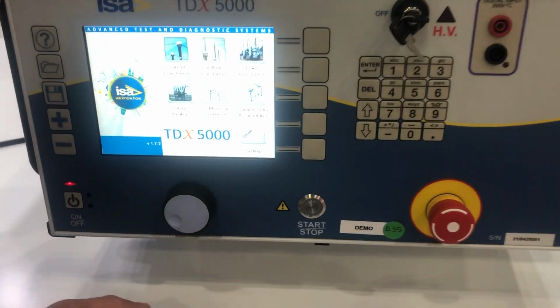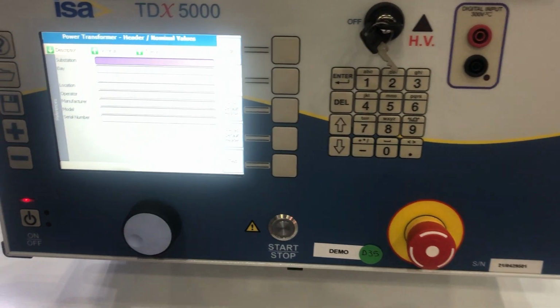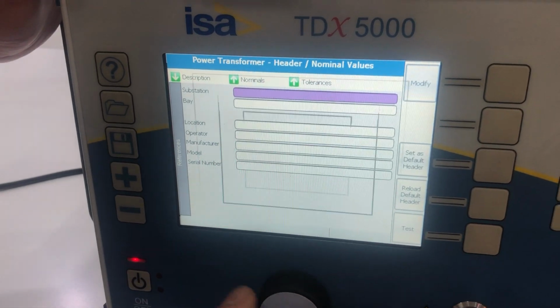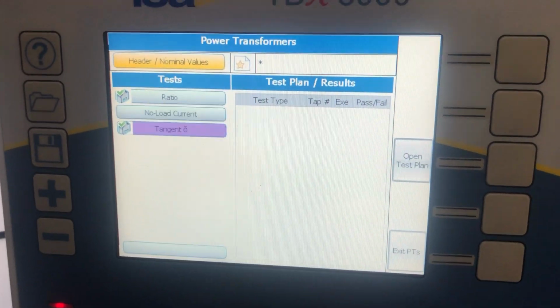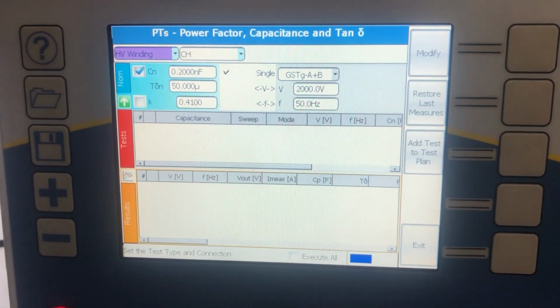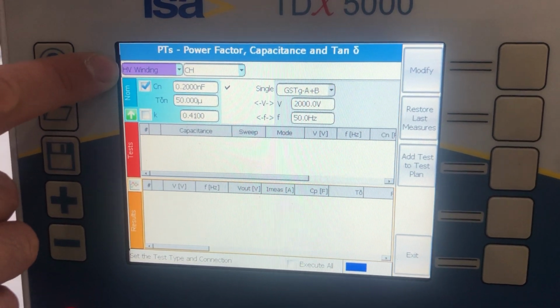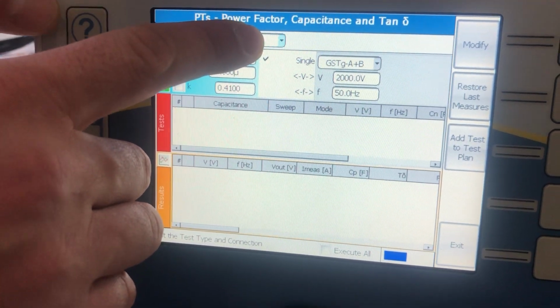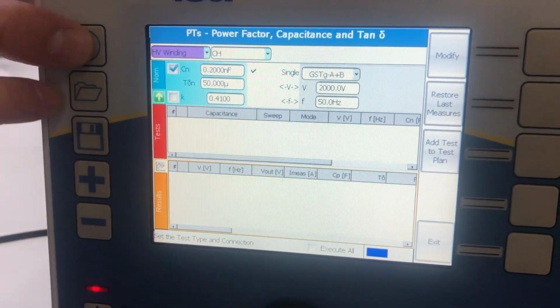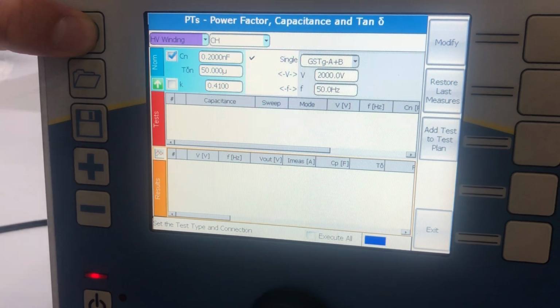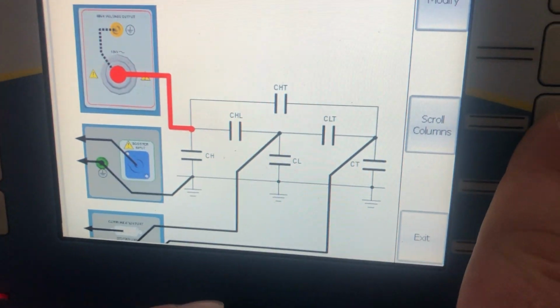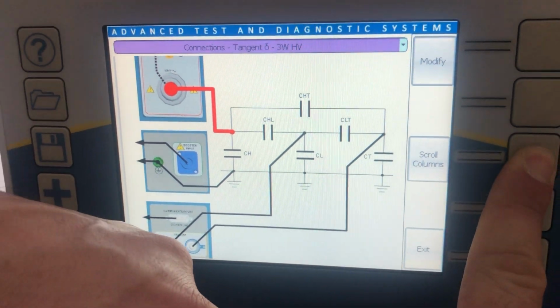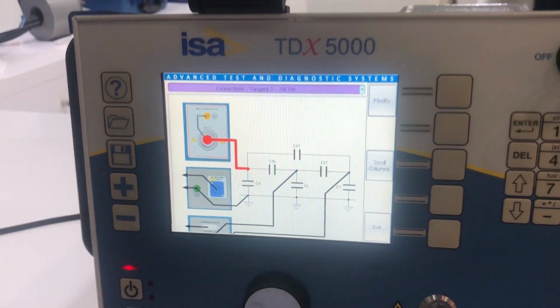You just choose the power transformer, then you press test, and after that, when you say tan delta, you just need to say where you have connected the high voltage generation and what you want to measure. If you are not sure how to make a connection, you press the question mark button and it shows you the help screen with how the connections need to be done.